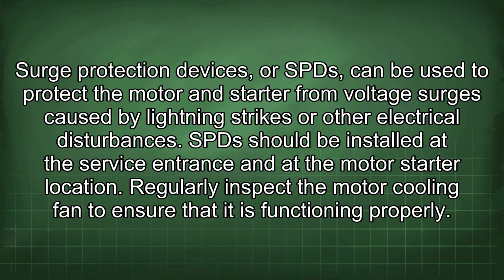Surge protection devices, or SPDs, can be used to protect the motor and starter from voltage surges caused by lightning strikes or other electrical disturbances. SPDs should be installed at the service entrance and at the motor starter location.